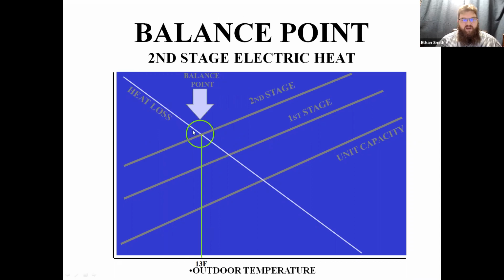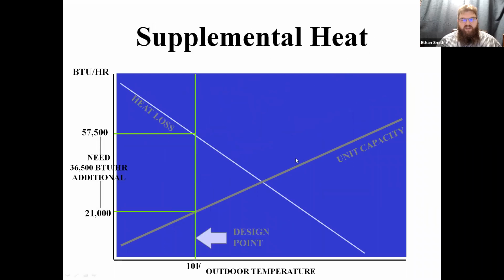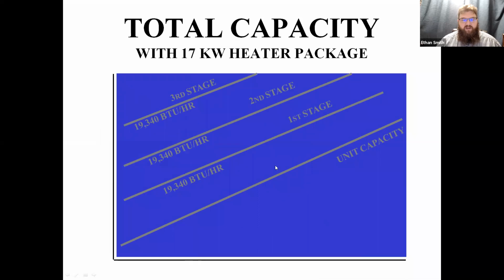Now, if my minimum design temperature is at 10 degrees outside, I may or may not need that third stage, okay? But as we saw in this slide back here before, each of my stages in this case is 19,000 BTUs. So how many watts is that, guys? How many kW is that heater? First one to get it wins. Maybe if you can get it before me, you win. Anybody? How many kW of electric heat do you need to generate 19,000 BTUs per hour?